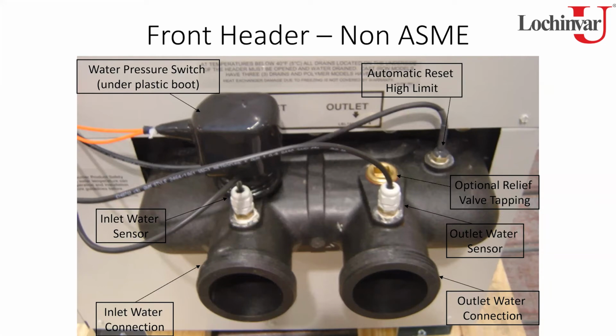When we look at this connection, again, this is our polymer header, so this is our non-ASME. Your inlets are on the left, outlets on the right, which is actually reversed from our other copper products. It's a little different there. You see your inlet and outlet water sensor screwed into the head. I believe the current models actually use stainless sensors. Those, I think, look like brass. Current models are stainless. We have switched those up a little bit.